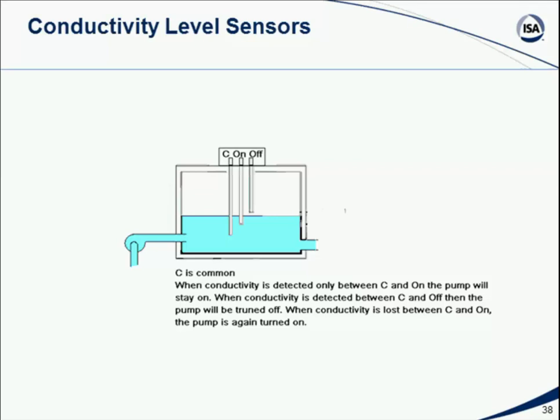When the fluid finally gets up to the third probe, then I'll measure between C and the off probe that there's now a drop in resistance and conductance. And by making the measurement between these various probes and determining how many of these probes I want to stick into the tank, I can make point measurements. Now, we do want to make an indication here. We're talking about point measurements. In other words, as the level goes up and down, we're not really trying to measure the change in level. What we're merely trying to do is make what's called a point measurement.